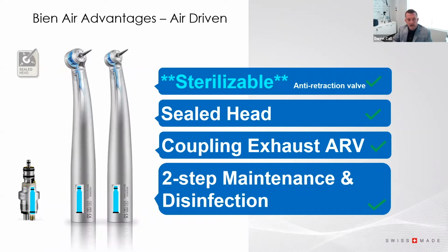The second place that cross-contamination is occurring is that the air-driven handpiece uses high-speed gas or air to spin a turbine. Unless the head is sealed, any aerosol that's generated inside the mouth, and any aerosol coming from the mouth or the tissue, will actually be sucked inside the burr hole because a vacuum is created. These things are spinning at 410,000 RPM. So a vacuum is created, and contaminant is sucked in the burr hole and then exhausted back down through the handpiece into the dental handpiece tubing and then into the dental delivery unit. And those parts of the dental delivery unit are not being sterilized or even disinfected.